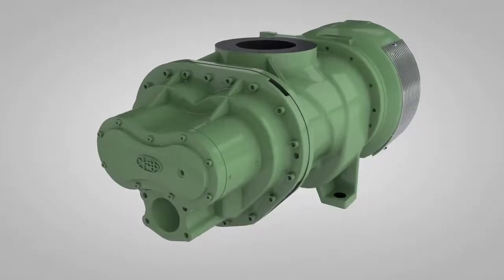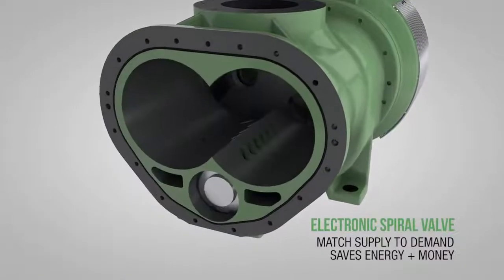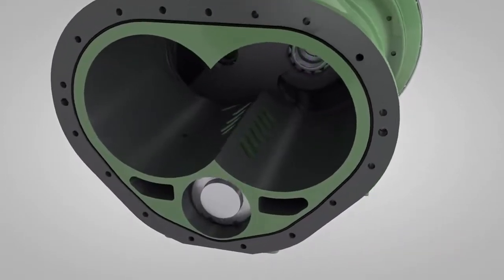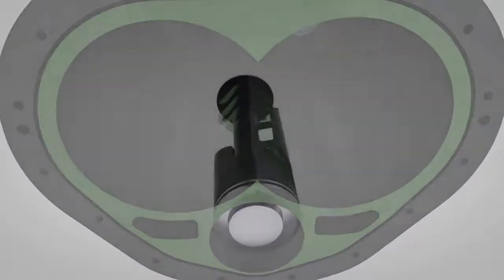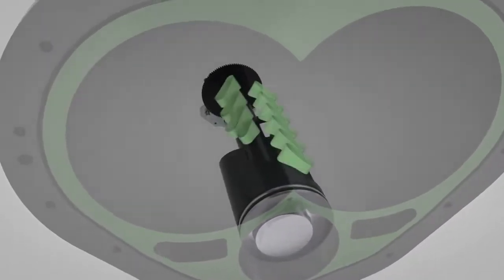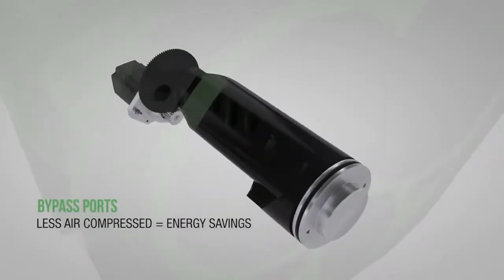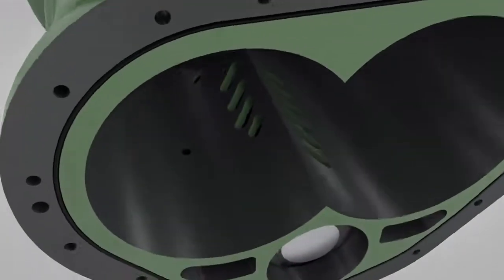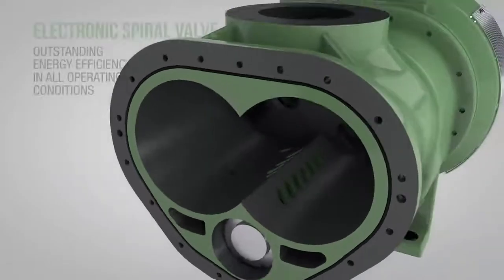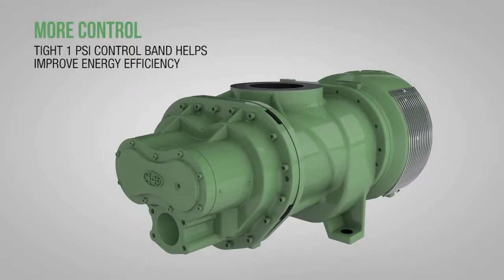Key to running a compressor efficiently is matching supply to demand. Sullair introduces electronic spiral valve technology — an energy efficient control scheme which matches compressor displacement to demand without reducing inlet pressure or increasing compression ratios. The variable displacement air end includes bypass ports. Progressively opening or closing the internal bypass ports changes the length of the rotor used in compression. Closed, more air is compressed; open, less air is compressed, saving you energy and money. The Sullair electronic spiral valve provides outstanding energy efficiency in all operating conditions, including high elevation and dirty environments. The tight 1 psi control band helps improve energy efficiency.